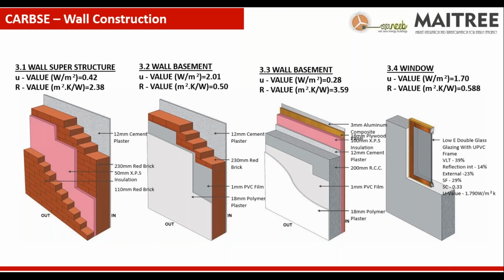Hence, what we have is a temporal mixed mode building. Temporal mixed mode means the building uses outdoor air as it is, without any treatment, whenever it is favorable. When the outdoor becomes harsh, we close our windows and start operating various kinds of air conditioning systems. We don't have just one system, but multiple systems, and depending upon the need in outdoor conditions, we operate these systems. That means the building must have a high-performance envelope.